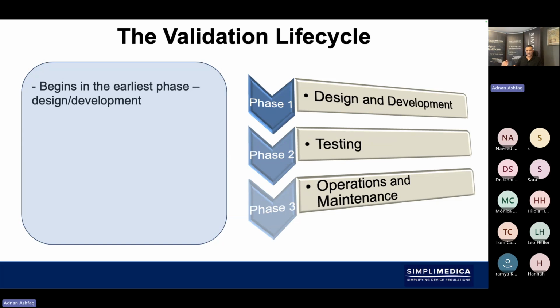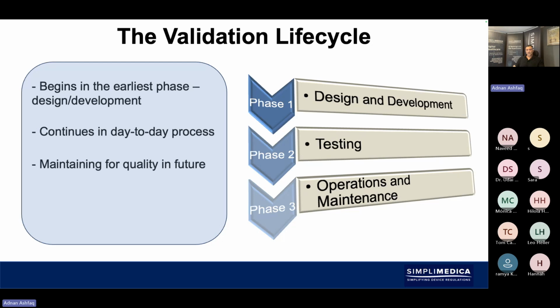So the validation life cycle itself should be looking at design and development. So design and development of equipment, testing the equipment, and then looking at operations and maintenance. It continues into day-to-day processes. We have to make sure that it's maintained for quality in future, and it continues until the termination of that process. So the validation must remain live. It's dynamic, and it's not something that would be done as a one-off and then we just forget about it. It's something that must be live, so it's a living system until the termination of that manufacturing process.